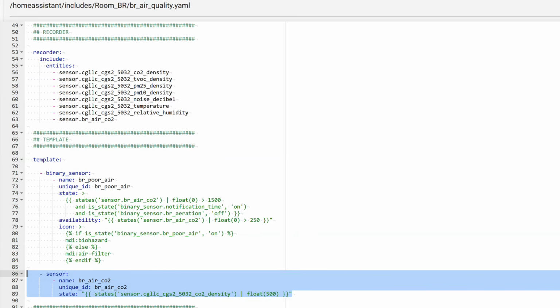Next comes the recorder block. In my case, only those entities that are explicitly specified are written to the database. In this case, these are all 7 readings sent by the sensor and the virtual carbon dioxide sensor in this room. Its code is highlighted a bit below and is identical to the value of the hardware sensor. The point is not to lose history in case of physical replacement of the air monitor. Then you simply change the name of the physical sensor in the template, and the history continues further without interruptions.